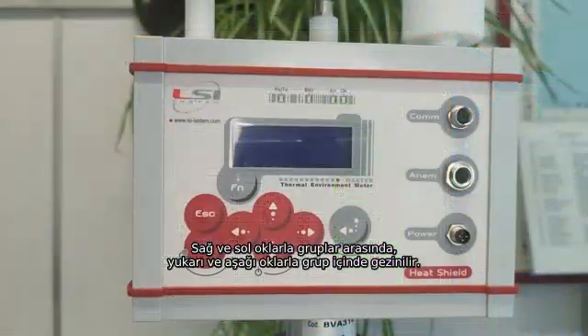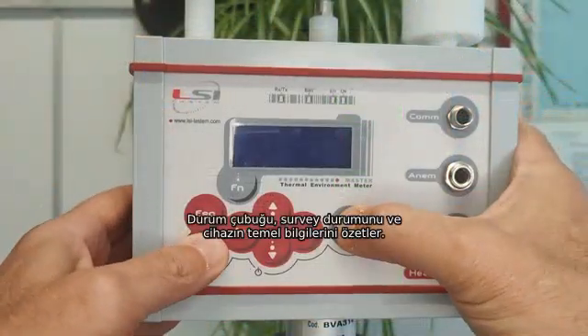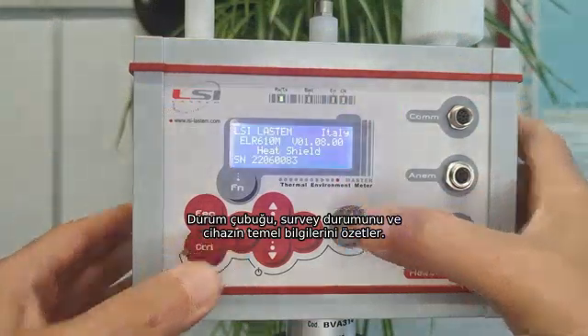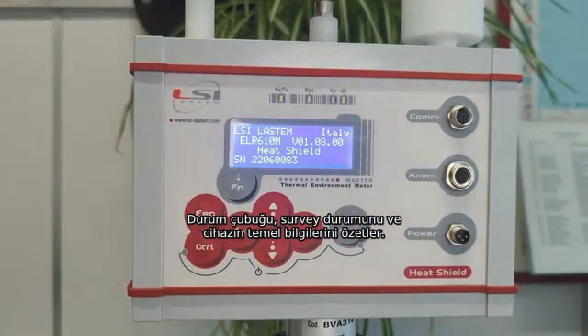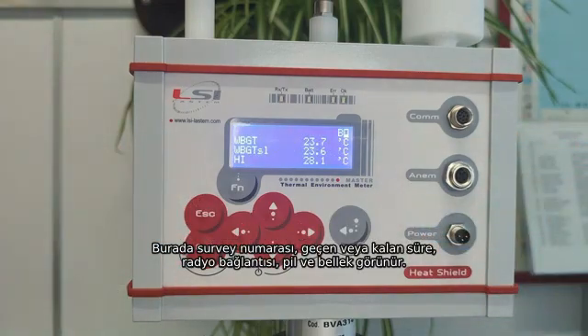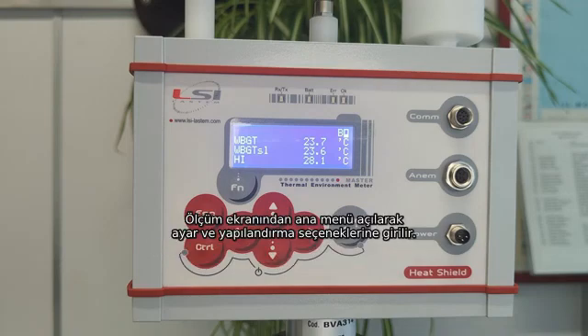Press the Ctrl plus Enter buttons to switch on the unit. Here it is possible to adjust the internal clock. Once you press Escape, HeatShield will immediately start to display the data using the settings stored inside the unit. In this example we have the WBGT values, using the without and with solar load formula, heat index, humidex index.